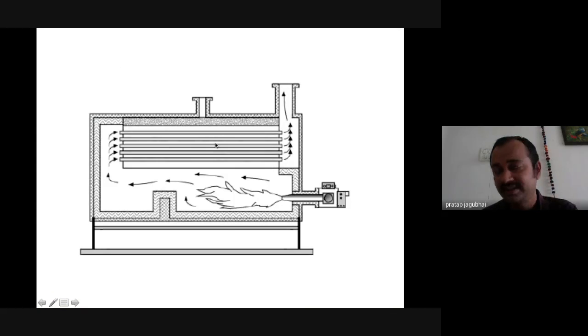Now, this is a more detailed view of the oil and gas fired boiler, which we have shown earlier also. The oil and gas fired boiler is simple in construction. We can say that it is a combination of passes. The first pass is the furnace, where the radiation is taking place, where the air is getting mixed with the fuel with the help of the burner. After this, the flue gases pass through the second and third pass, and due to convection, heat is getting transferred. So in totality, the radiation and convection zones transfer the heat to make the water into steam, and then the flue gas comes out from the chimney.